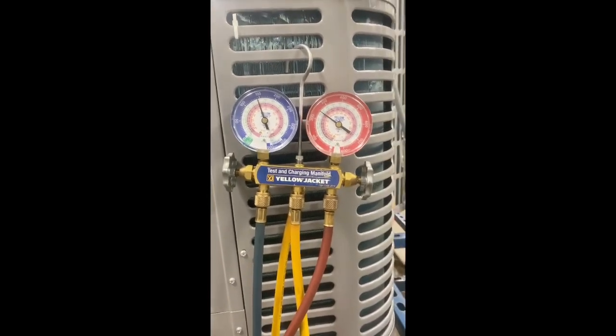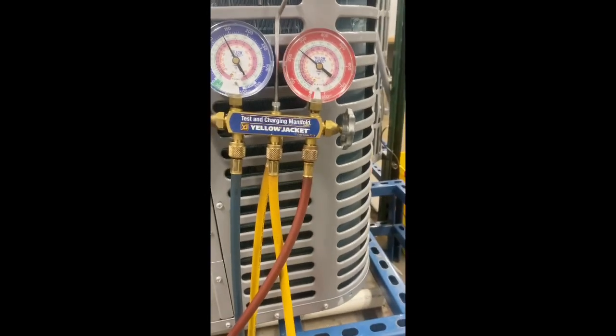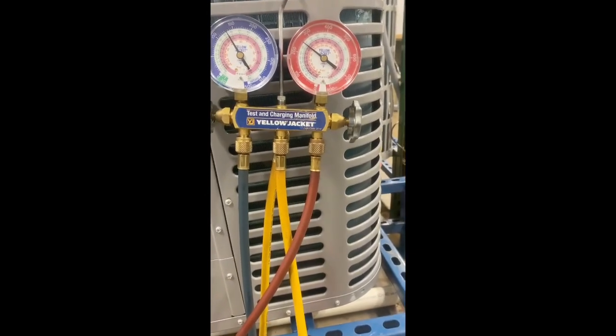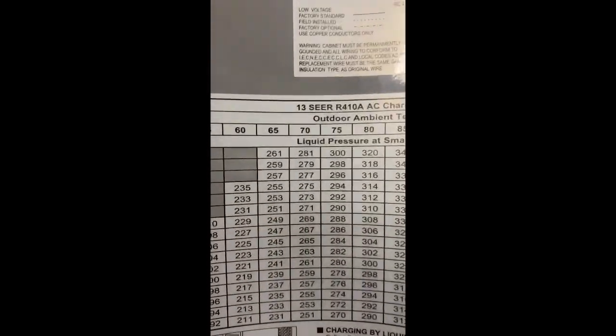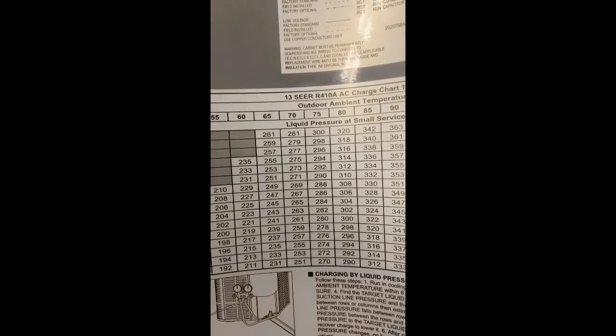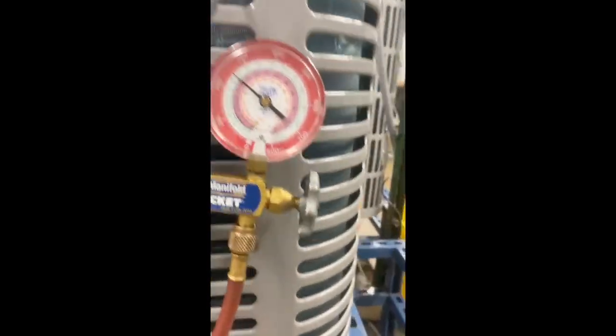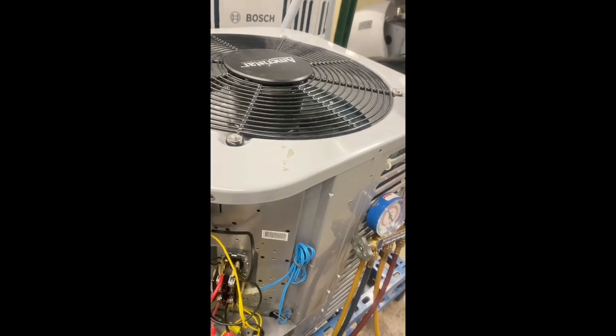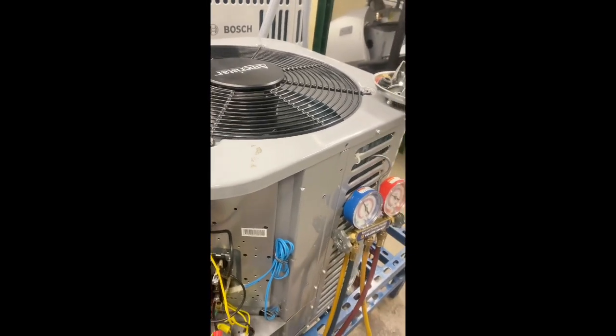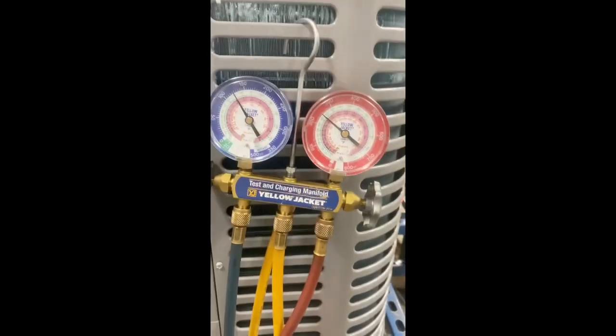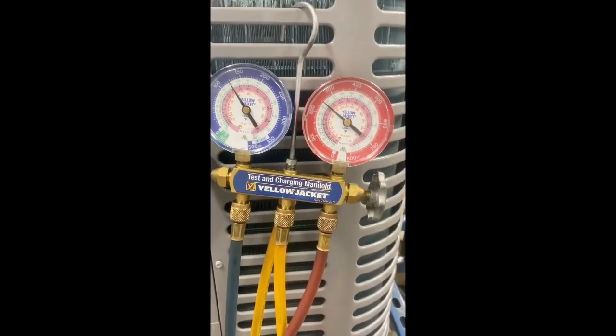With the machine running and cooling the area, it's going up on the high side here, but it's not as high as it needs to be. Checking the outside temperature, it's about 70, so that's calling for a somewhat higher temperature on the high side. But the problem is I found out recently that if there's no load to dissipate the heat from the condensing unit, the fan isn't going to work as hard because there's nothing to really dissipate. You're in a building, basically.